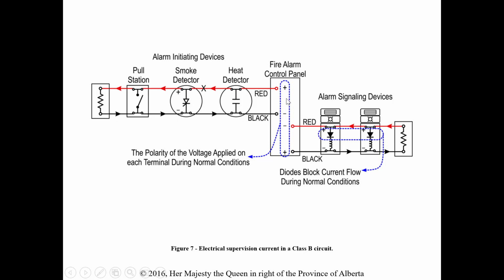And that's going to give us a value of current that the panel is going to recognize as a normal condition. Now, if we have an opening, like they talk about having a break where this X is, we basically have lost every device on this side of the break. So only this device would be working at that point, and the end-of-line resistor wouldn't be in the circuit any longer. So we would know at the panel that the break had occurred. It just wouldn't potentially be very easy to find. So you know there's a problem, but you don't know where the problem is.